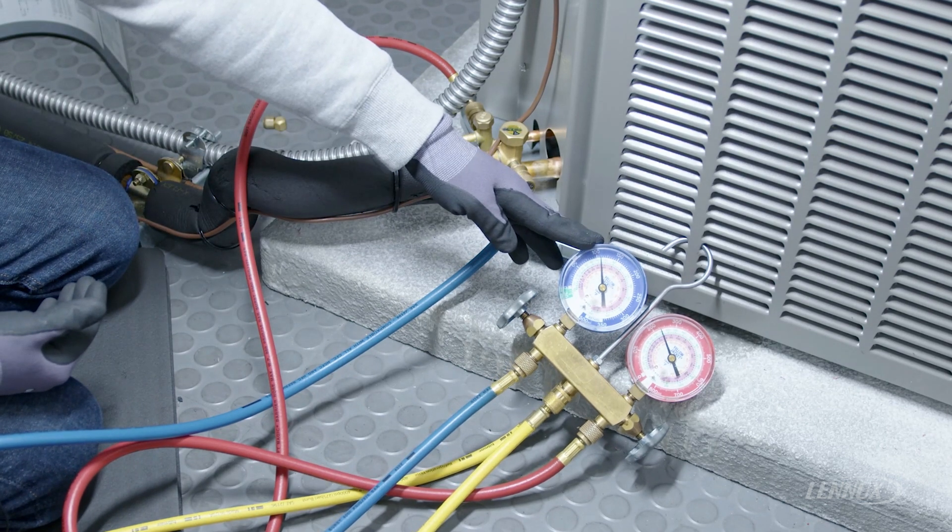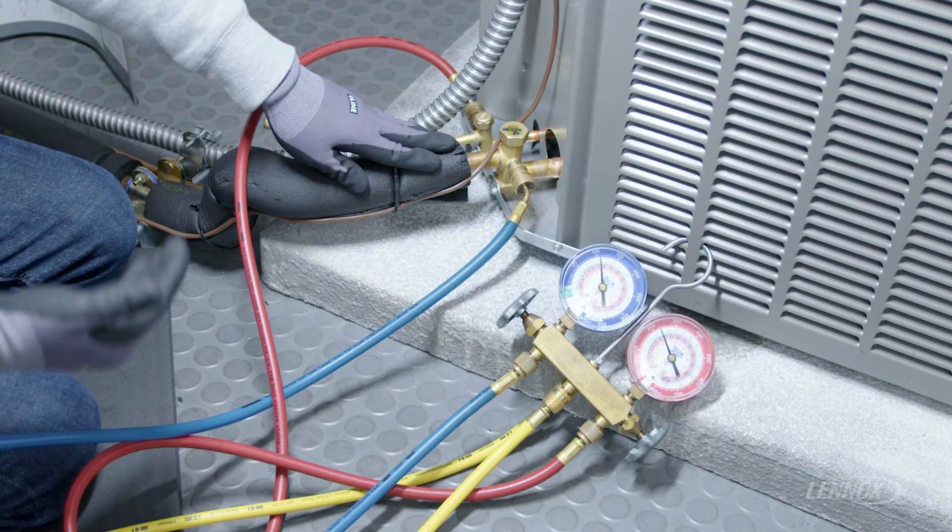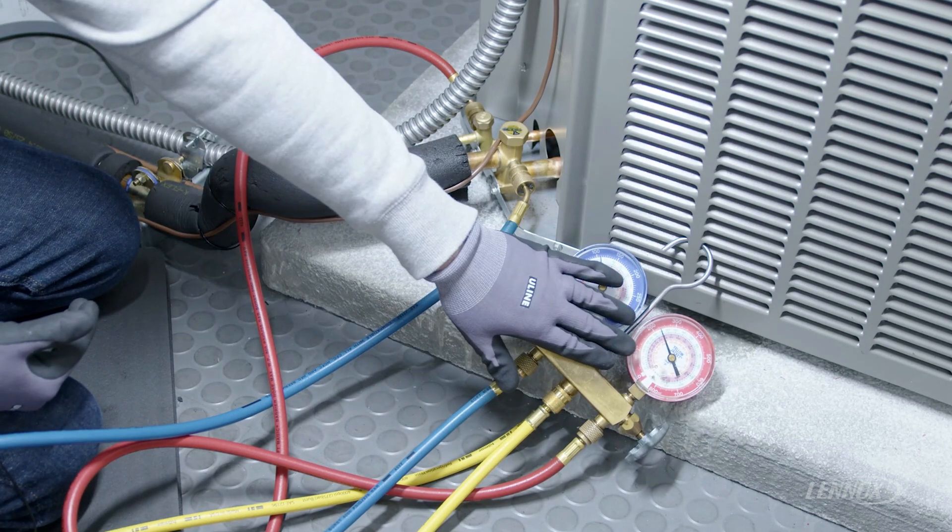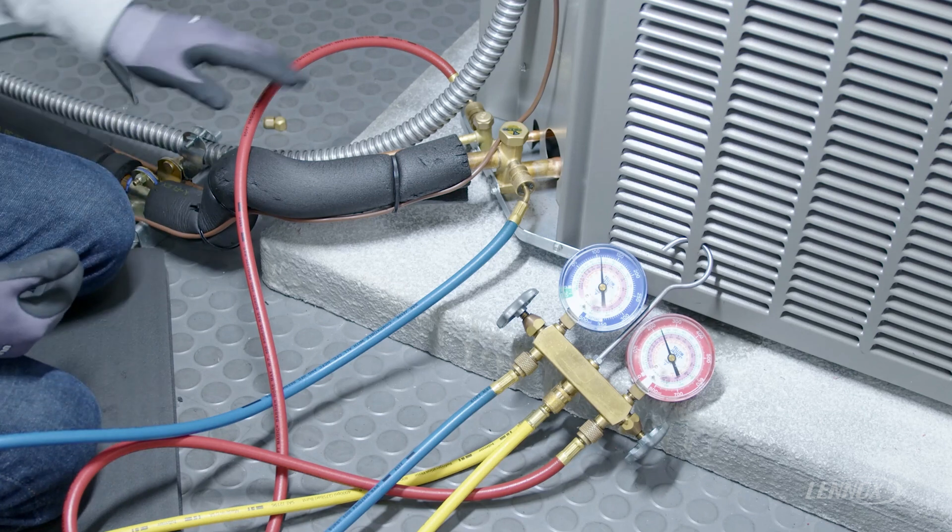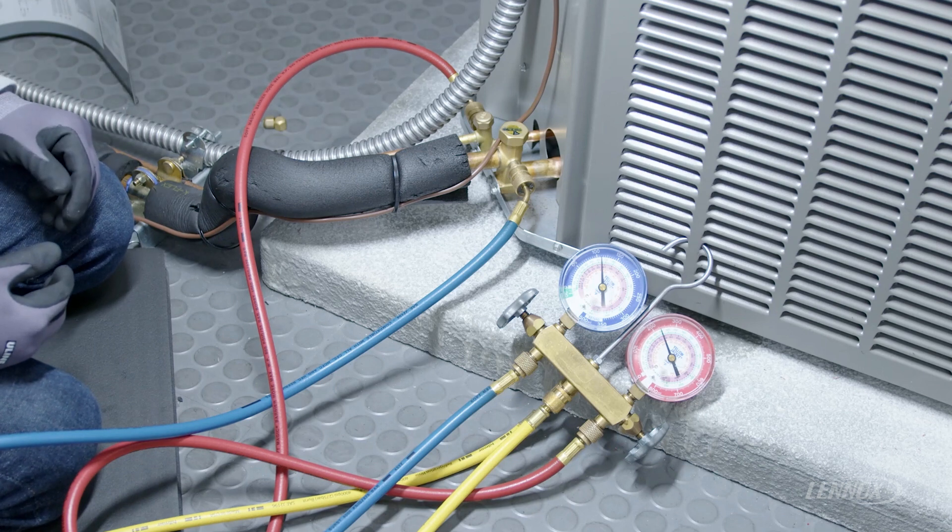Again, the blue side is going to be representative of our suction line pressure or our low side, which is indoors, and the red gauge set will be indicative of what our liquid line is doing or our pressure of the refrigerant in the outdoor condensing unit.